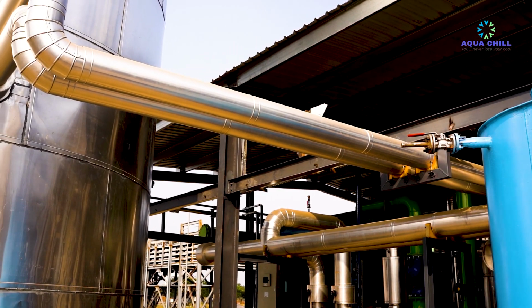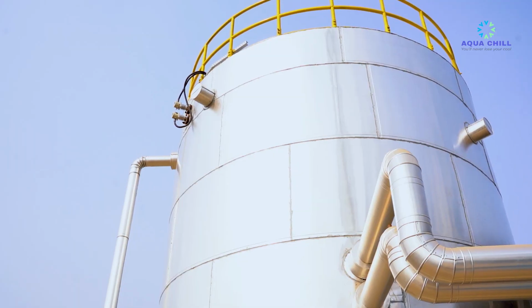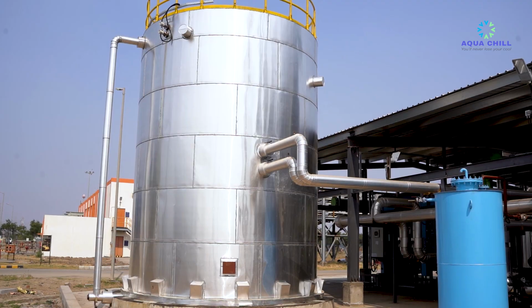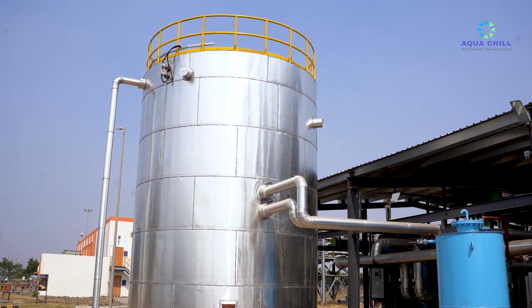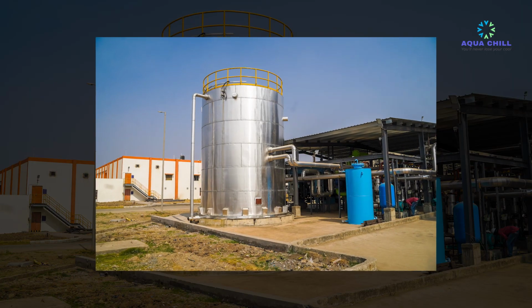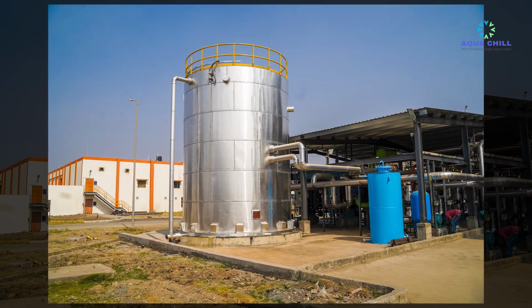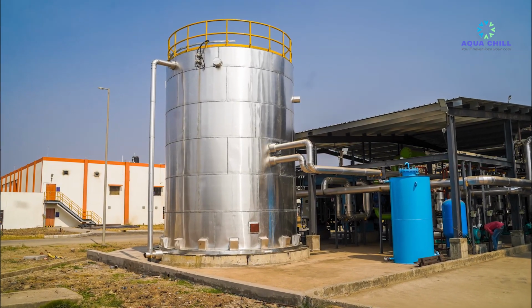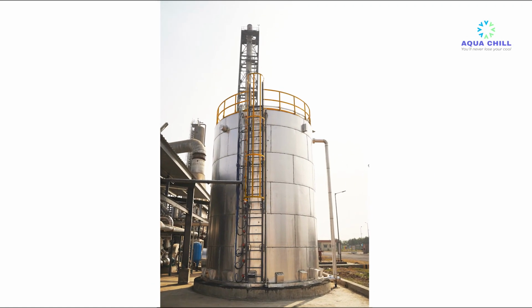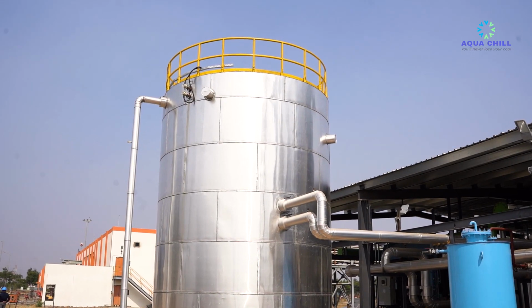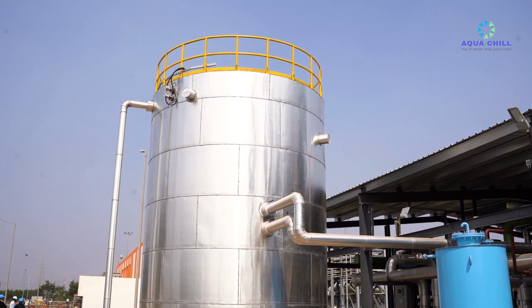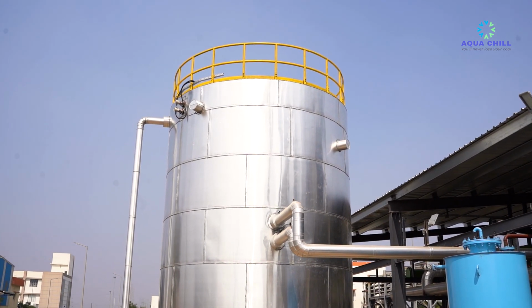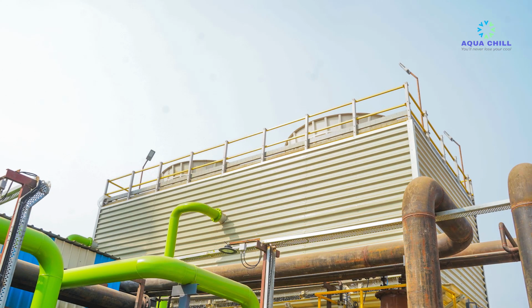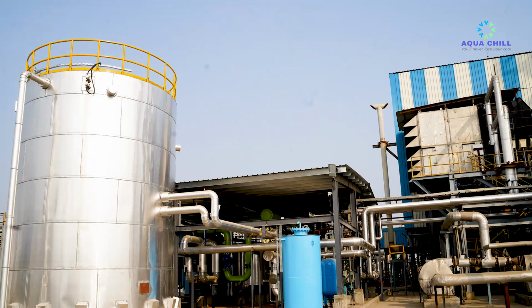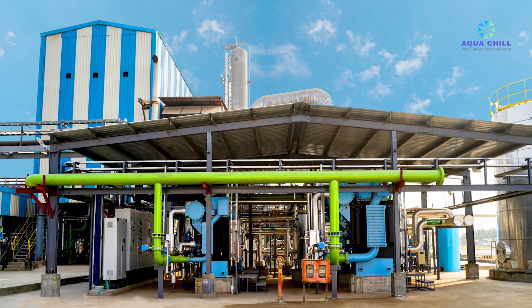Aqua Chill also addressed another constraint at the plant, which was associated with absorber tower cooling. Earlier, the entire tower used to be cooled by cooling tower water. Now, a part of that cooling is being achieved with chilled water, thus improving the productivity of the line. The absorber tower is a 45-meter tall structure. There were challenges in selecting the right size of pumping circuit, which was done by Aqua Chill with great precision. Using the best industrial practices in design and execution, Aqua Chill has installed this unique system that has increased the compressor output by 15%, if not more.